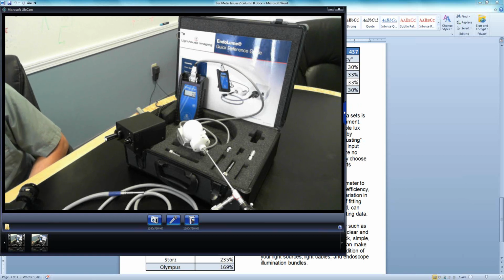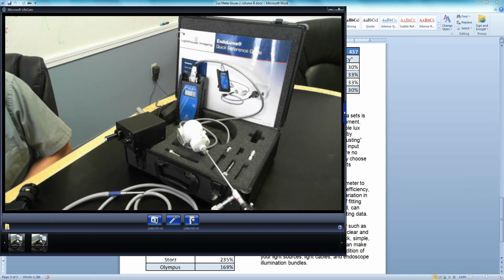Oh, no, there are two key things to remember there. First, the light source that we provide is an LED light source, so it has an expected lifetime on the order of 50,000 hours. However, even if it did have some variation, the way you use the EndoLume is you always test the light source input and then measure the light output of the device you're testing. So it doesn't really matter whether the light bulb or light source is brand new or has a very high output, you always scale to it.